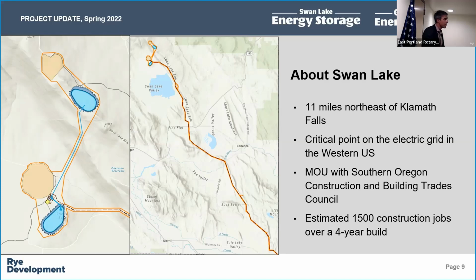So talking about water use, this project is a one-time fill of the system of around 4,000 to 5,000 acre feet of water into the system. And then we're going to use about 300 acre feet of water per year to offset evaporation, basically. For the Goldendale project, a little bit bigger, I think it's a 9,000 acre foot initial fill of the system, and about 400 acre feet of water per year will be needed to offset evaporation in those locations.